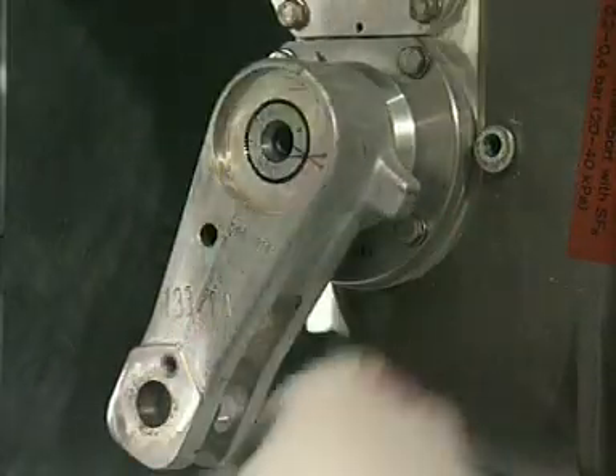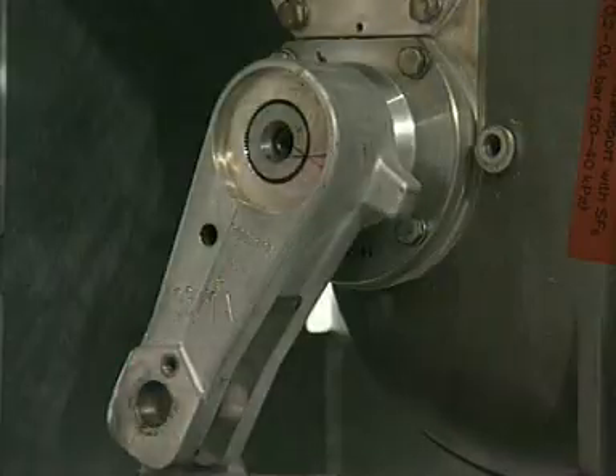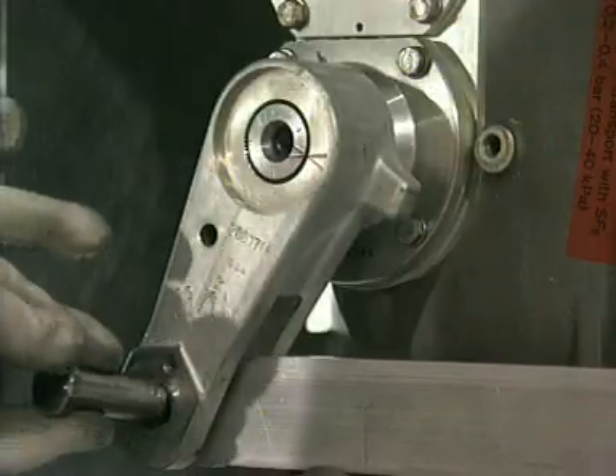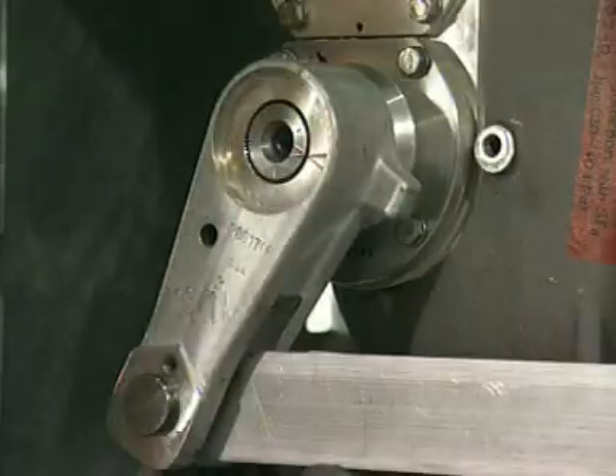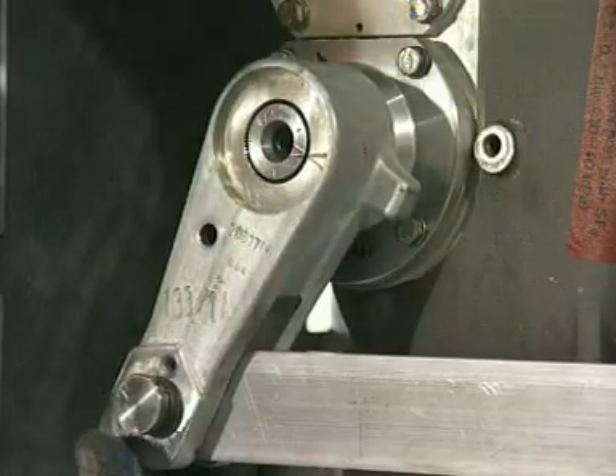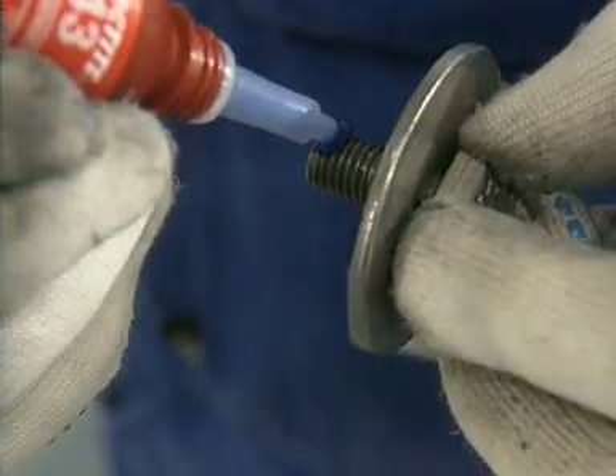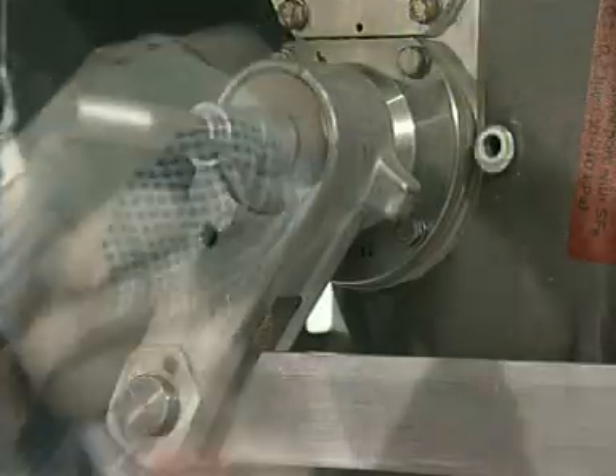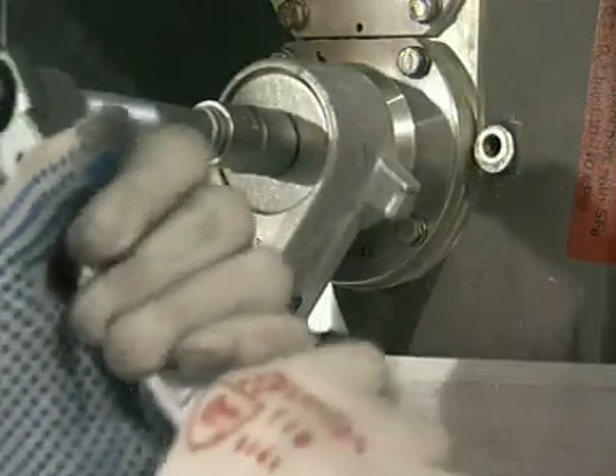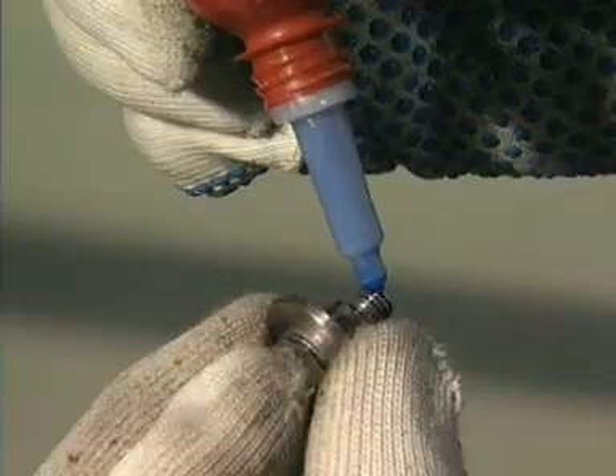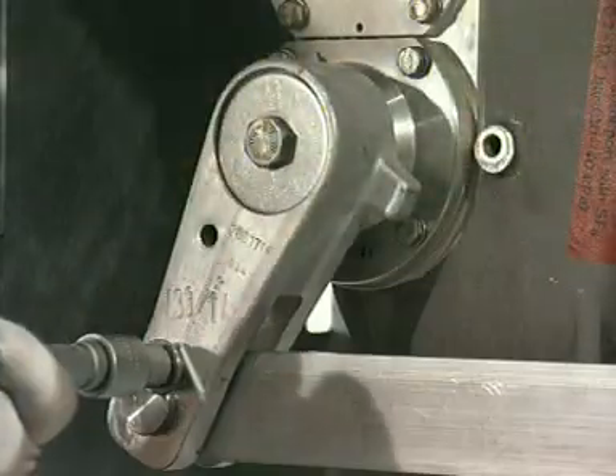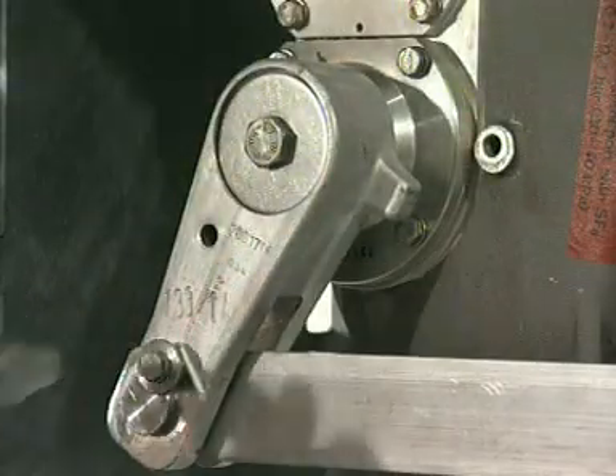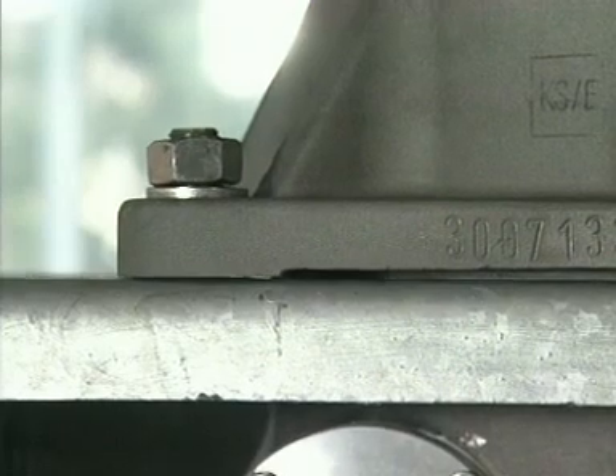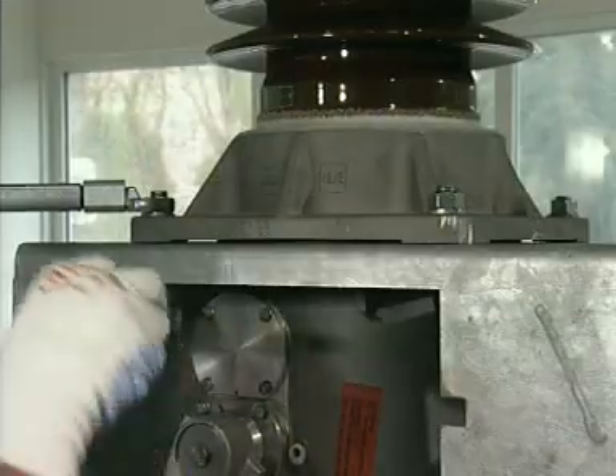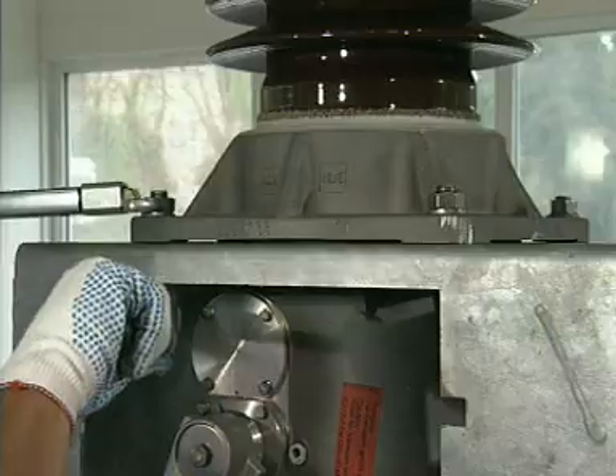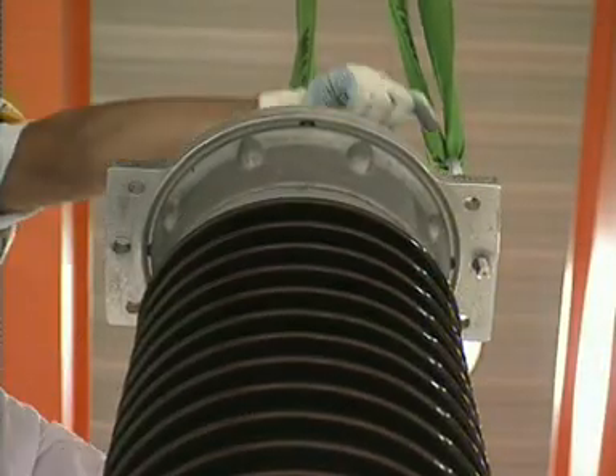Mount the lever so that the coupling pin can be easily inserted. Fasten the lever using a bolt, liquid locking and washer. Insert the greased coupling pin and fasten it using a bolt, liquid locking and washer. Lower the pole column completely. Tighten the bolts using a torque wrench and remove the rope loops from the connecting flange.